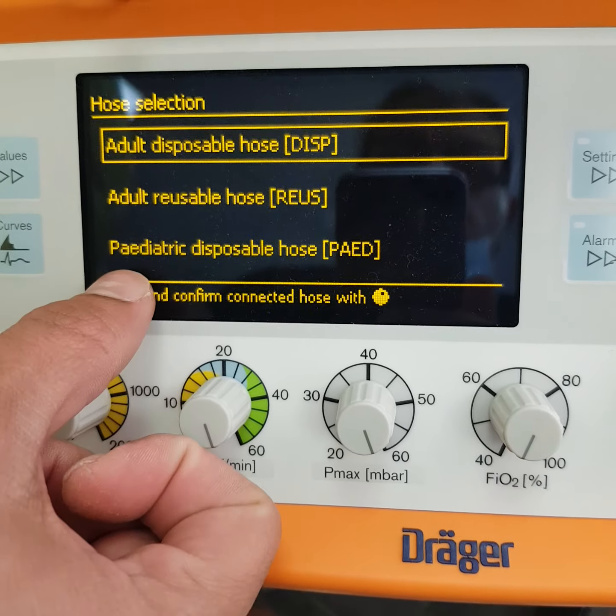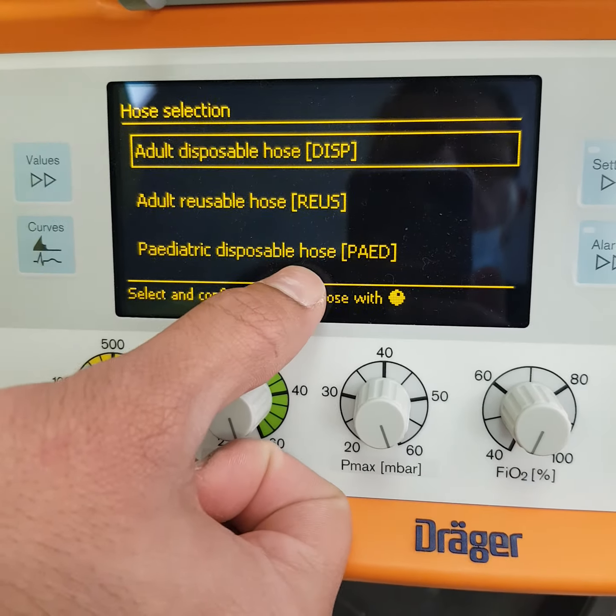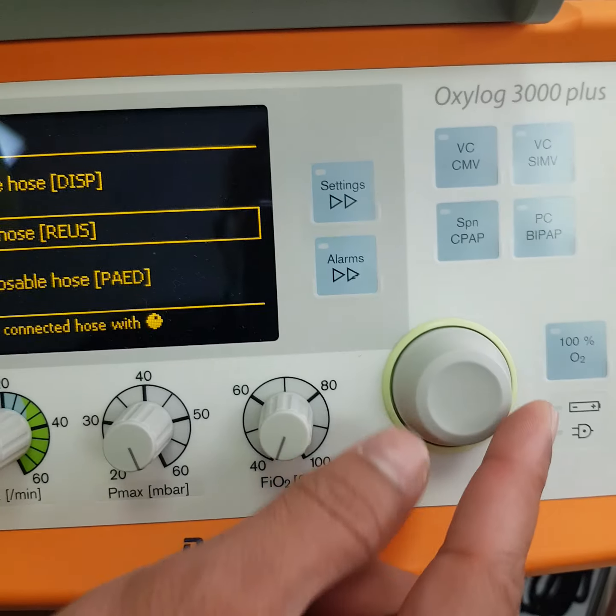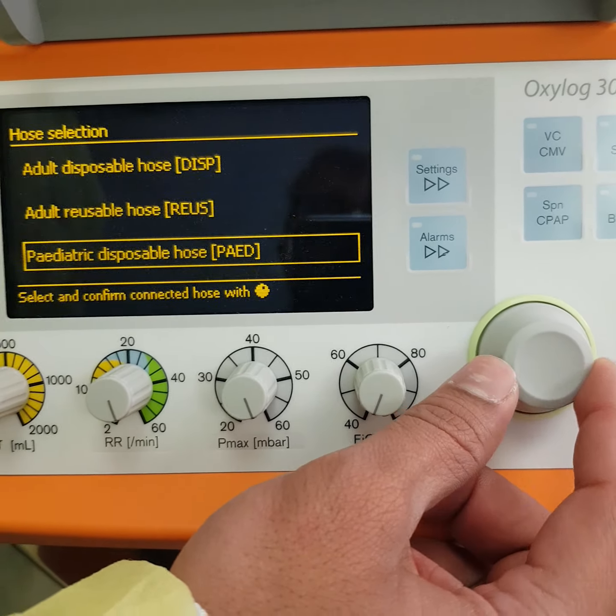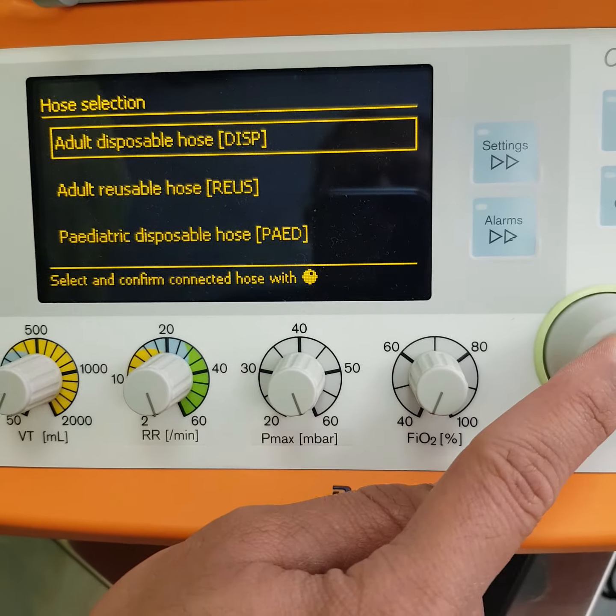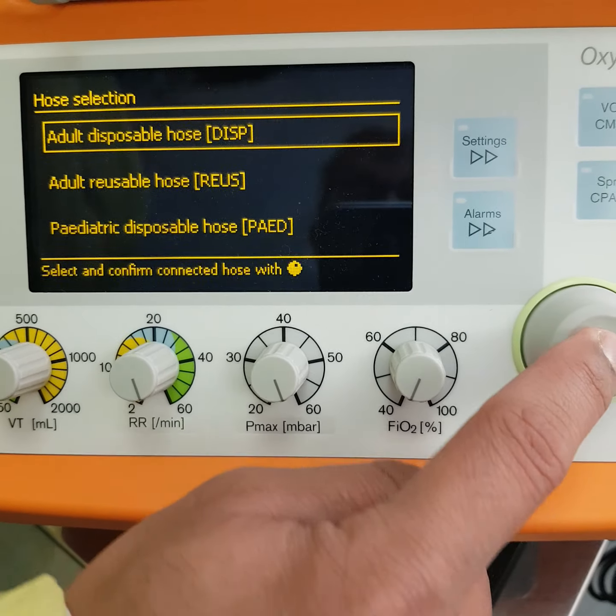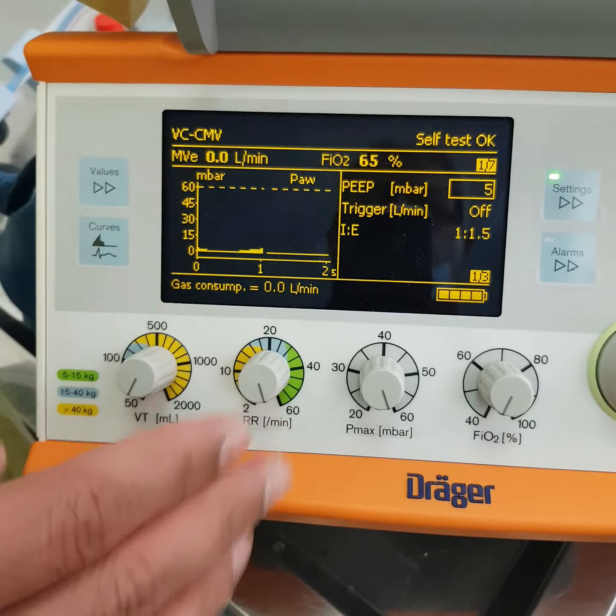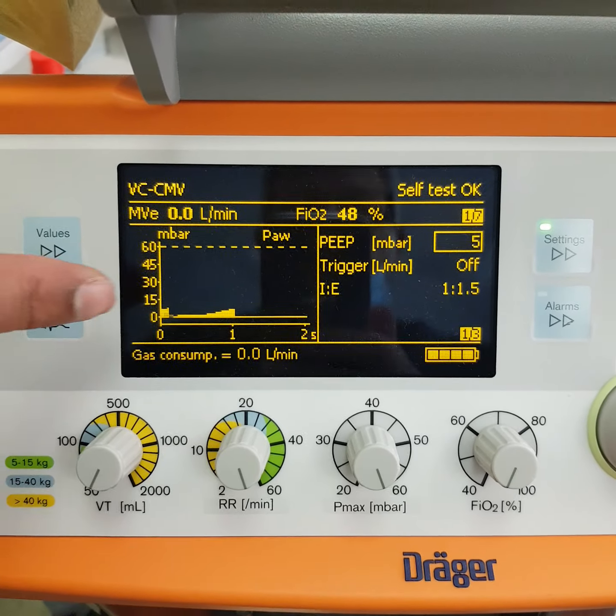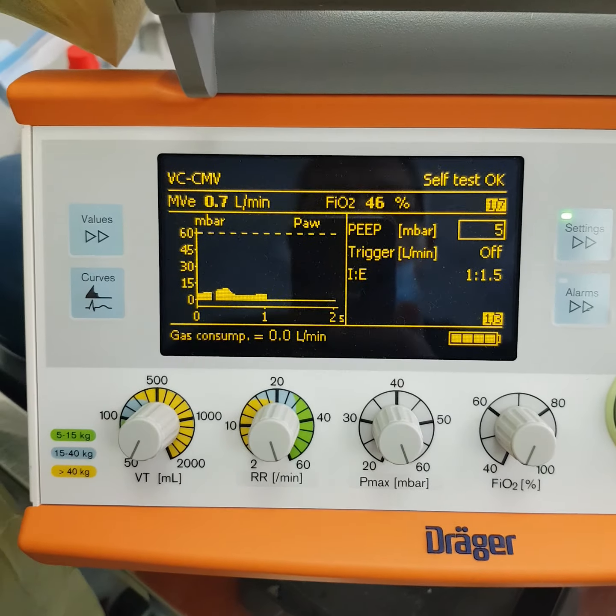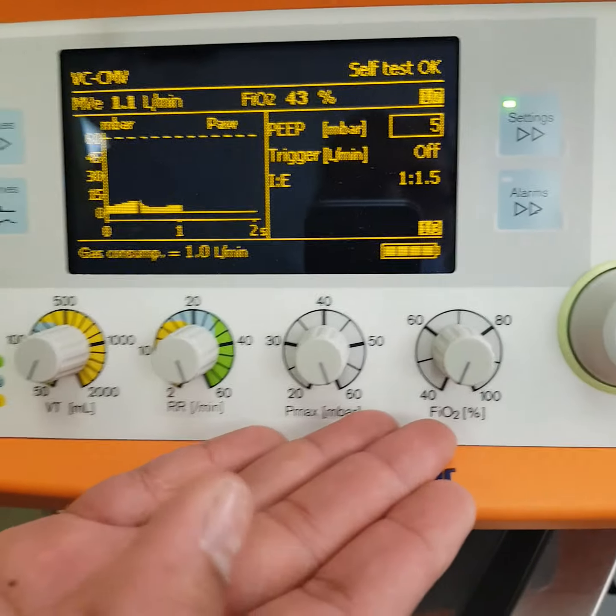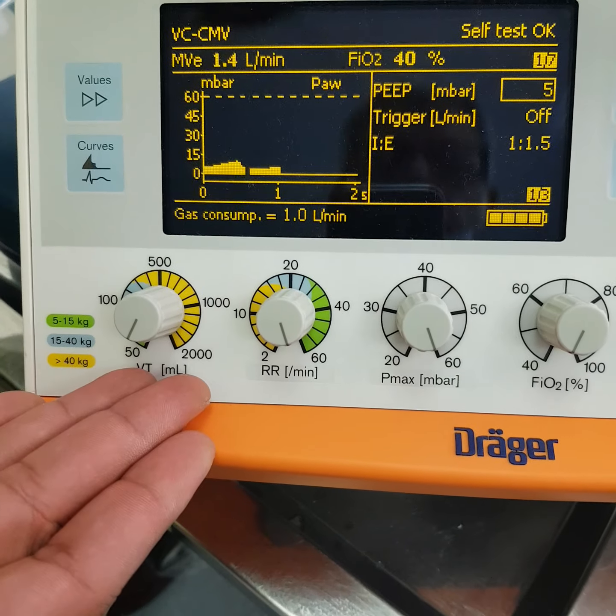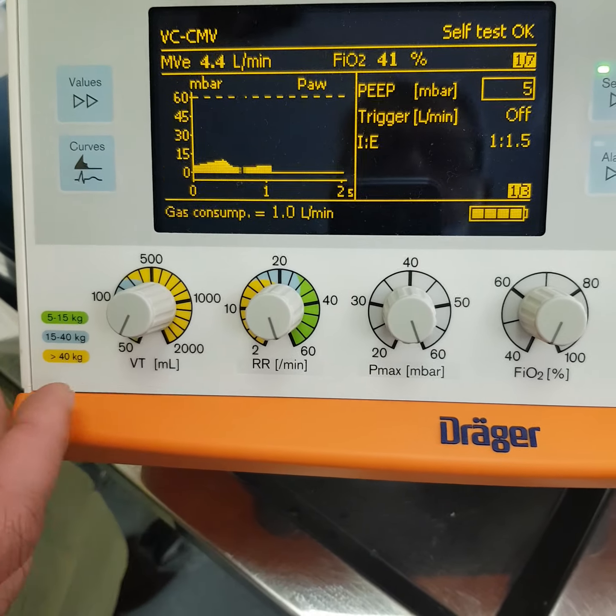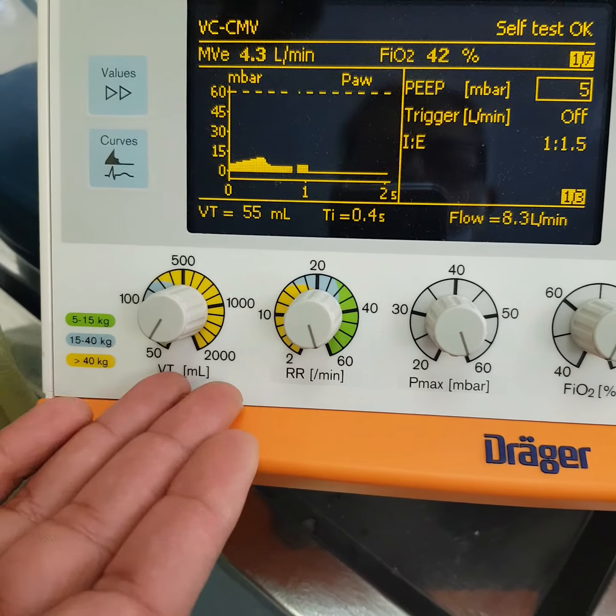If you want to use it for pediatric, we have a pediatric disposable hose, which can be selected by the rotary knob. So here you rotate and select what type of circuit you are using. Right now we are using adult disposable, so confirming. Once you confirm, you can start immediately. You can see that the machine has started ventilating, because all the settings and key parameters are kept outside for easier configuration. So here are the outer parameters.